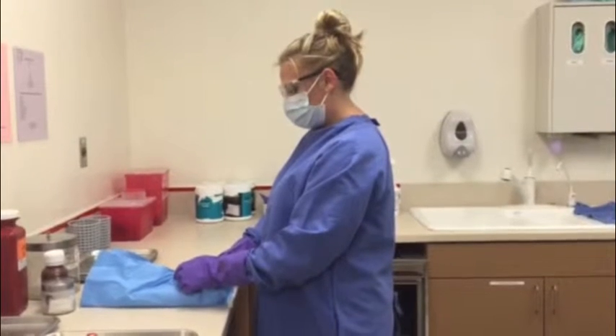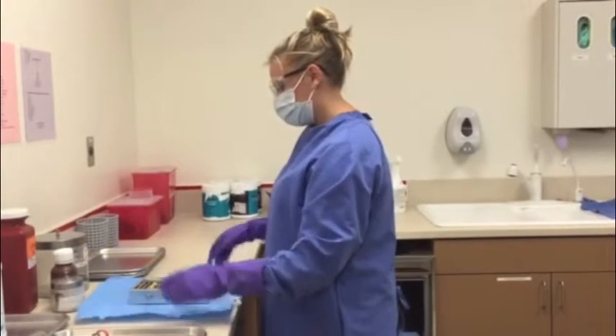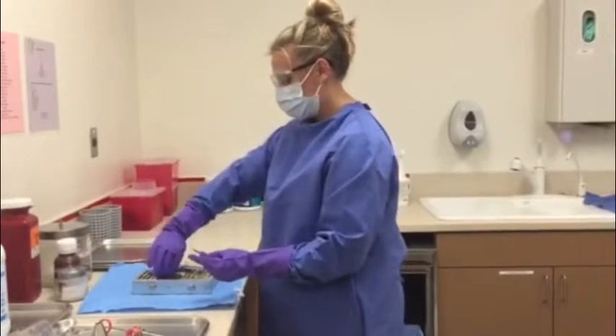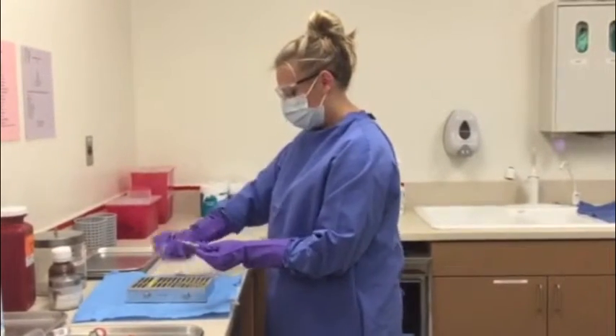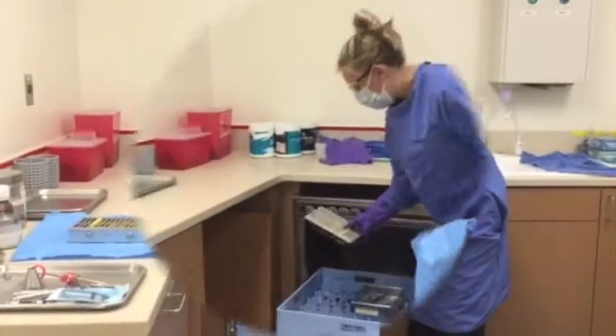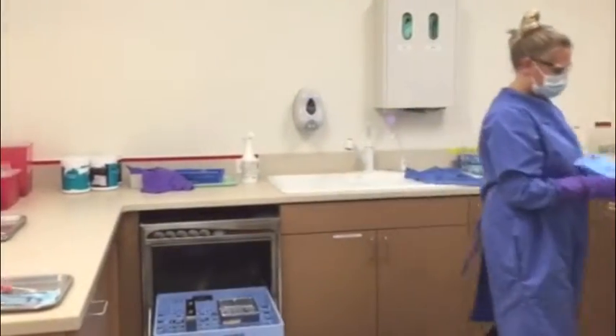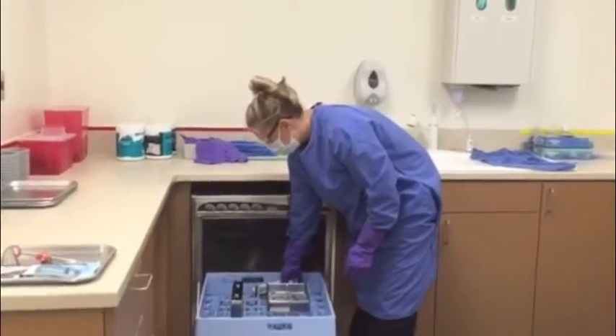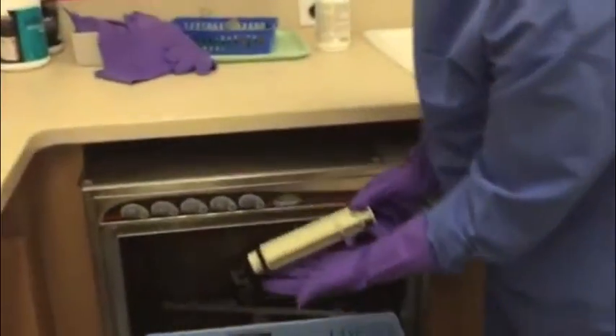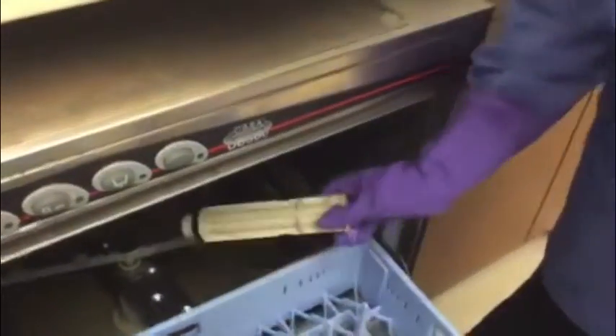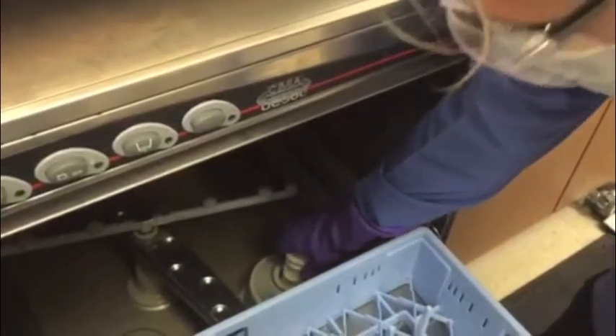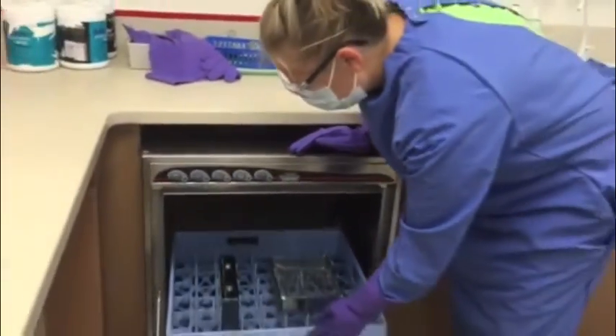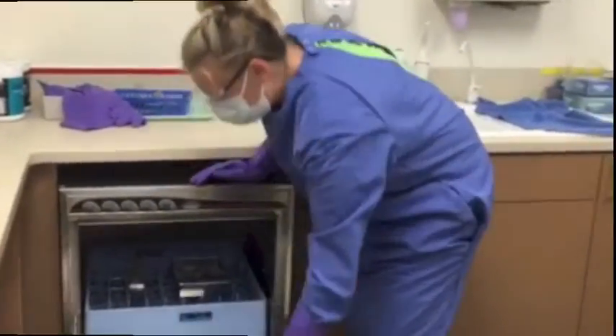Now Goldilocks has reached the instrument washer. She puts the loose instruments in the basket and puts the cassette into the instrument washer, and discards of the paper in the waste receptacle. She then places the plug in the drain. Turns the washer on. It starts to heat up.